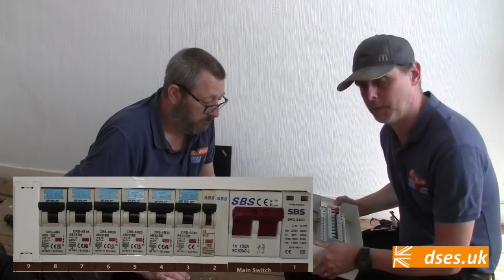Obviously RCBOs, they're all double pole anyway, as most RCBOs are, although instead of a single cage clamp at the bottom, you've got a line and neutral cage clamp. The MCB is interesting, because notice it's a little skinny fella - what's that, 9mm? It's effectively half the size of a standard MCB, and it's got a blank next to it. SBS tell me they're changing that design, a new design is coming out shortly, so that will be interesting.